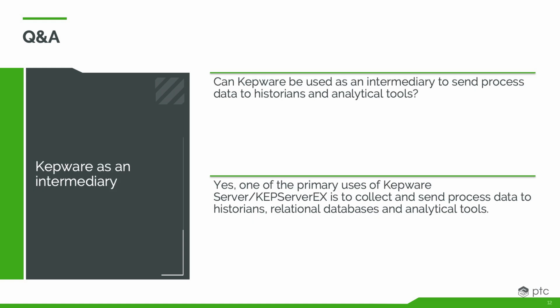Thank you for asking if Kepware can be used as an intermediary to send process data to historians and analytical tools. Absolutely, that's one of the primary purposes of Kepware over time. Those OEM relationships we've had since the mid-90s have often been front-ending historians and analytical tools. GE Historian, for example, almost always uses a Kepware utility to communicate with hardware and software assets on the plant floor. Canary Labs Historian and OSI Pi are similar. Many historian and analysis products exist, but they don't focus on creating protocol translation tools, so they have limited support for network languages. That's where Kepware's enterprise best-in-class HTTP interface or OPC UA server binds nicely to these historians, handling the really hard work of communicating high volume with determinism down to the plant floor.